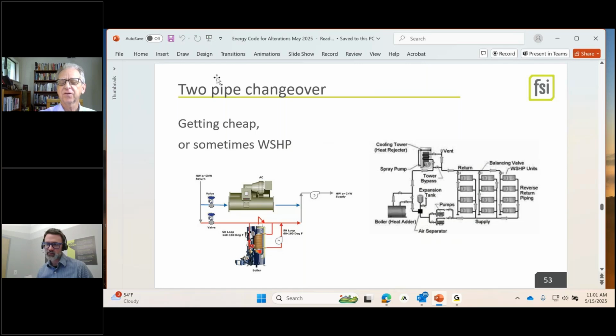Those are the ones with steel pipes that corrode down to really skinny pipe. It's all about water treatment. If your maintenance people were on it, those pipes can live a 40 or 50-year life, and it's usually only at central plant level that maintenance folks are really deep into their water treatment.